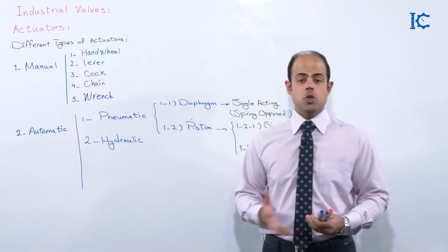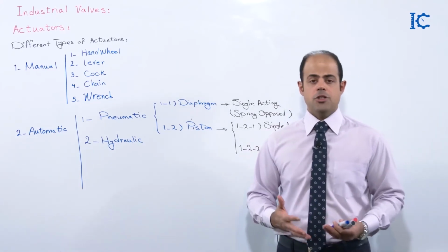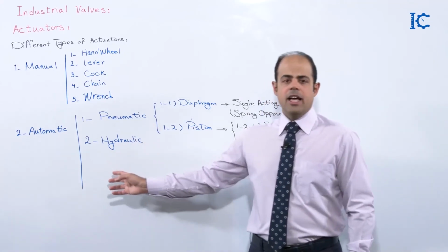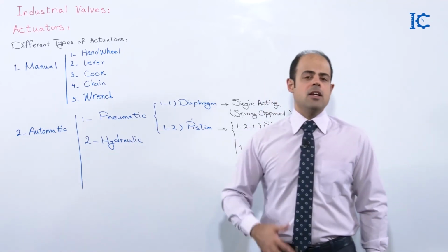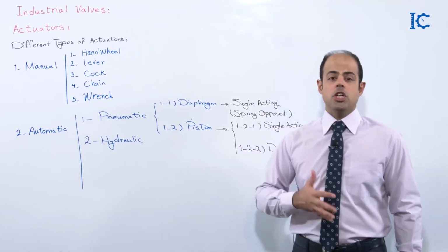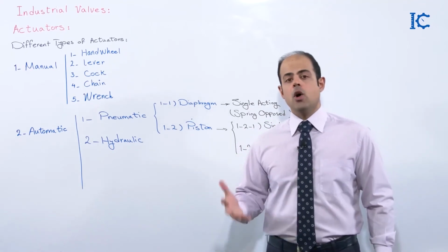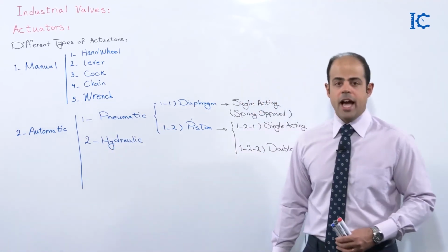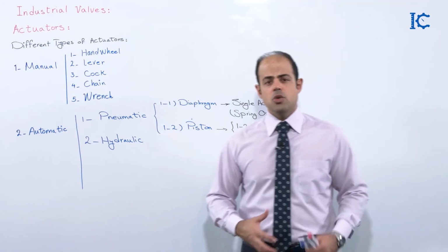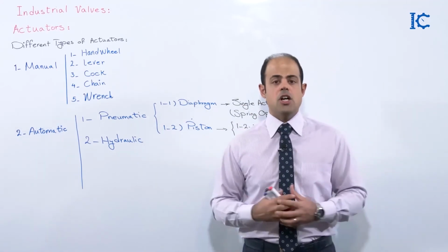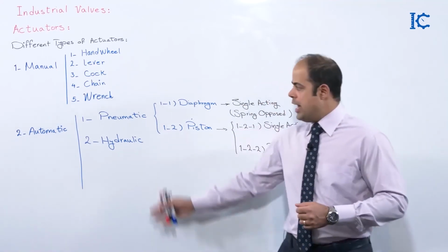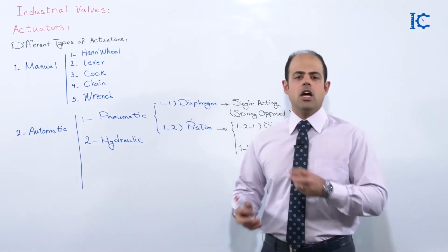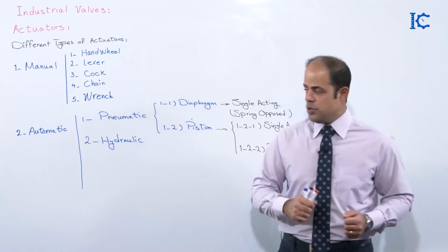In this case, you need to have some hydraulic type of actuator to open or close the valve. Such as, for example, valves like GOV, gas operated valves, or GOOV, gas over oil valves, which work with the help of hydraulic actuators. When you have even larger valves, you must use the hydraulic ones, and with the help of some piston jacks, you can open or close the valve.